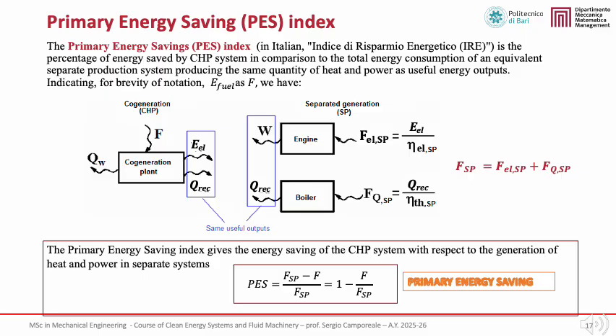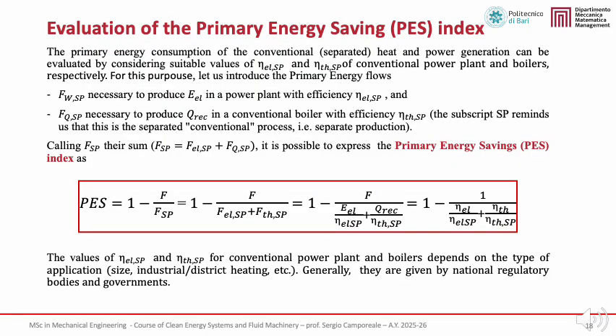as high efficiency cogeneration. Now we describe how the PES index can be evaluated in practice, following the methodology established by the EU Cogeneration Directive. The primary energy consumption of the separated reference system is calculated using harmonized reference efficiencies for conventional technologies. In particular, we introduce the electrical efficiency of a conventional power plant, eta EL, SP, and the thermal efficiency of a conventional boiler, eta TH, SP, where SP stands for separate production.